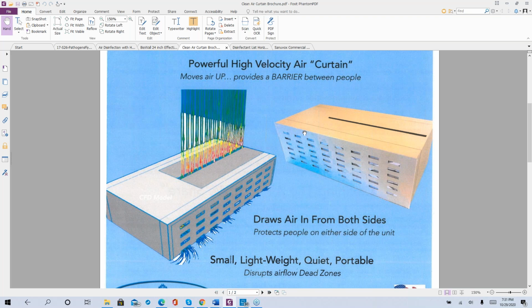And the high-speed plume here, the high velocity, will mix the air in the room and drive down concentrations quicker than would otherwise be done by a device. There's a couple of ways to go about solving this problem, Paul, and you're quite aware of them, I'm sure. The static pressure on these HEPA filters is so high that they generally use a big surface area to get the air through them. So they end up being big, kind of clunky.